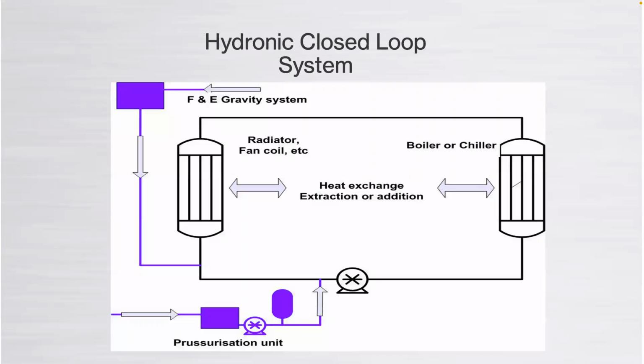A very, very simple schematic, but essentially we've got a circulation pump pushing water around either a boiler or a chiller, where we're either heating or cooling that water, and then we want to deliver that energy into a space through either a radiator, a fan coil, or air handling and so forth. There are some older systems in the UK, not so sure in the US market, where you'd find a feed and expansion gravity system. Not ideal because obviously the system is open to atmosphere.